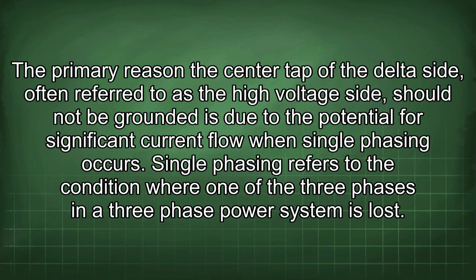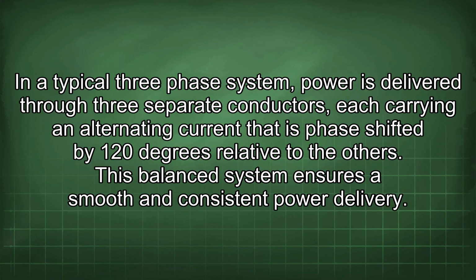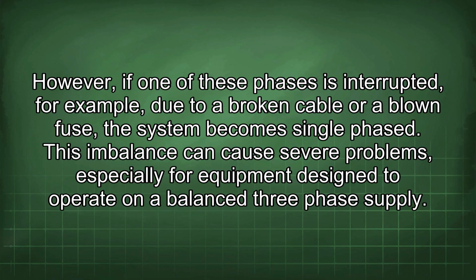Single phasing refers to the condition where one of the three phases in a three-phase power system is lost. In a typical three-phase system, power is delivered through three separate conductors, each carrying an alternating current that is phase-shifted by 120 degrees relative to the others. This balanced system ensures a smooth and consistent power delivery. However, if one of these phases is interrupted, for example, due to a broken cable or a blown fuse, the system becomes single-phased. This imbalance can cause severe problems, especially for equipment designed to operate on a balanced three-phase supply.